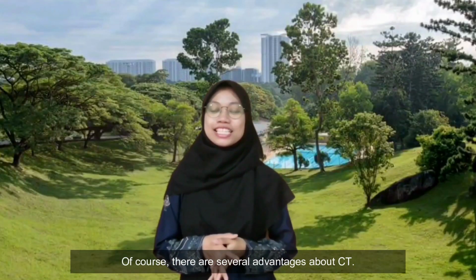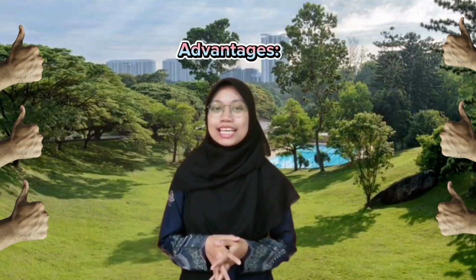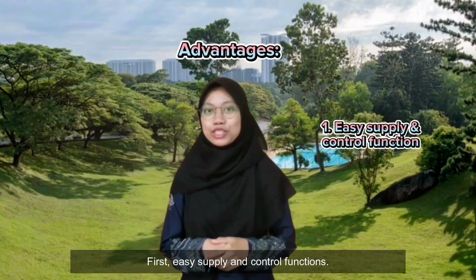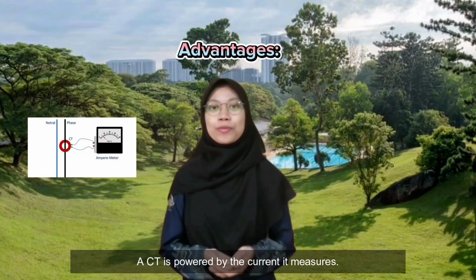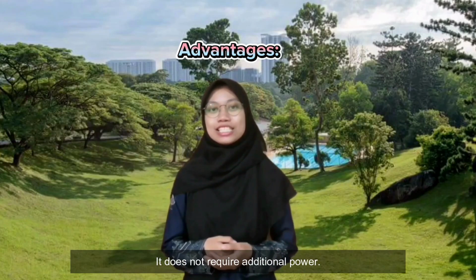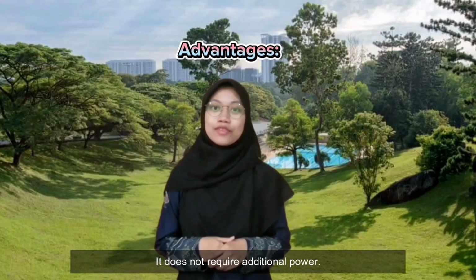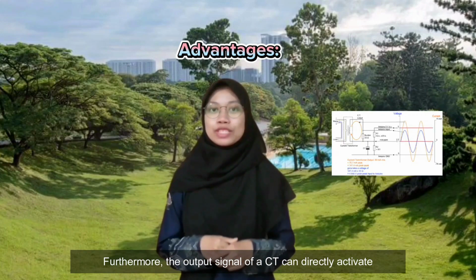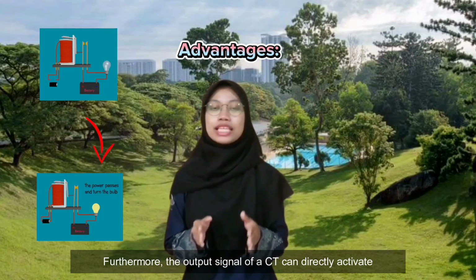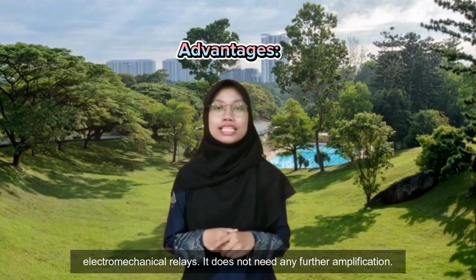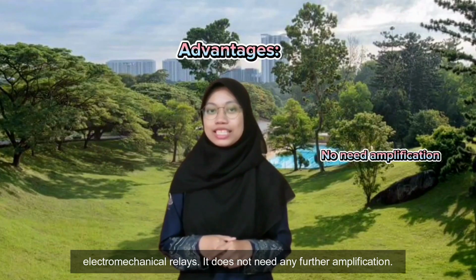Of course, there are several advantages about CT. First, easy supply and control functions. A CT is powered by the current it measures. It does not require additional power. Furthermore, the output signal of a CT can directly activate electromechanical relays. It does not need any further amplification.